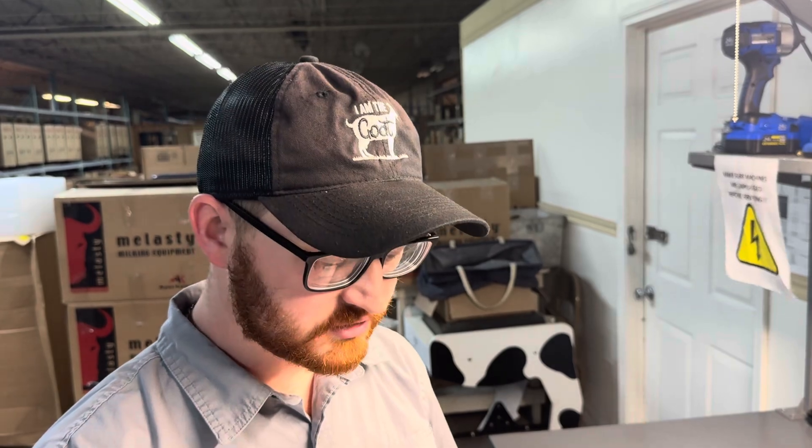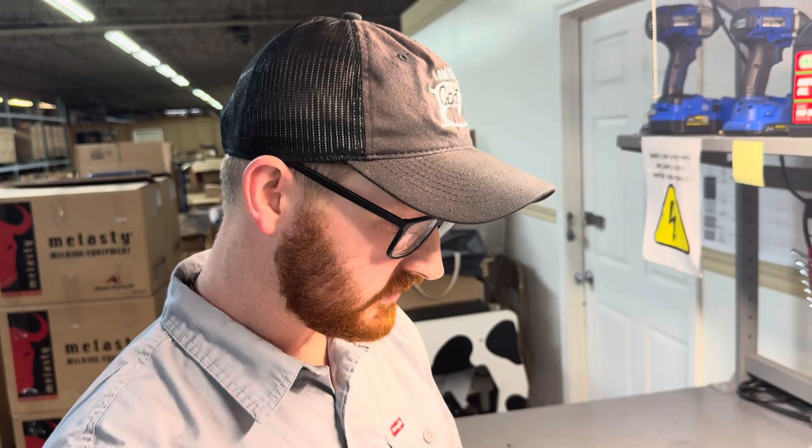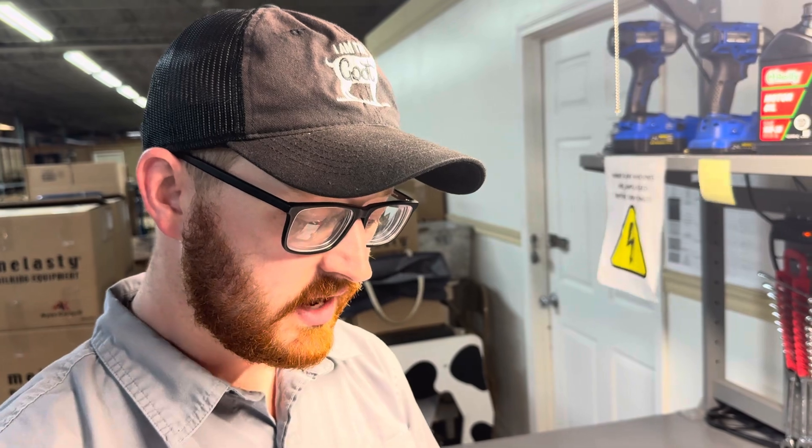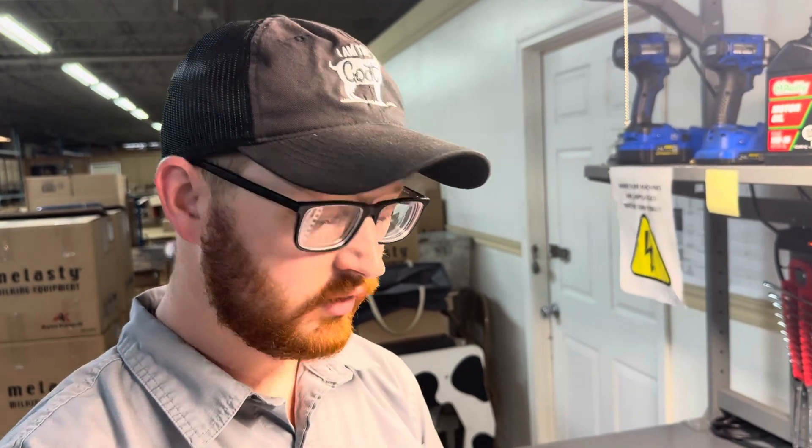A question you may have is: how do I know if my capacitor is bad? With the testing we just completed, the range we want to be within is: our 75 microfarad capacitor should be no less than 71.43 and no higher than 78.75 microfarads. For the 35 microfarad capacitor, we don't want to be below 33.3 or above 36.75 microfarads. If your machine has 50 microfarad capacitors, your minimum is 47.6 and maximum is 52.5 microfarads.